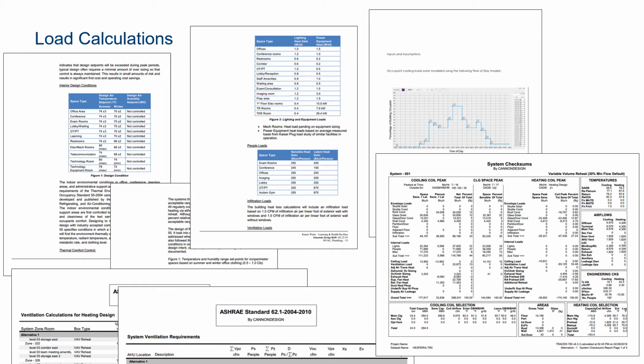But one of my favorite examples was a boiler plant that we were reviewing. The engineer had sized a set of boilers for some buildings and wanted our review. And so we simply pulled the utility bills. We looked at the natural gas bills for the last couple of years, and you can take one year's worth of natural gas and simply divide by 8,760 hours, come up with an hourly natural gas use at the site. You can even do that by month if you wanted to come out with an hourly natural gas use in February, for example. And the reason I remember this particular project so well is that one boiler, there were 3 boilers, but one boiler in the proposed plant was exactly 5 times the annual average hourly natural gas load. So the average condition was a 5-to-1 turn down on one boiler, and we had 3 boilers specified.